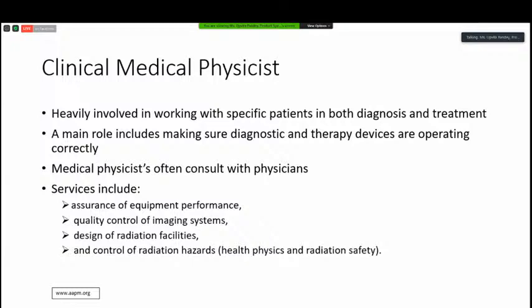A day-to-day job of a clinical medical physicist includes performing quality assurance on treatment machines, checking calibration, checking spatial accuracy of treatment delivery, and checking the quality of treatment plans developed by radiation therapists. They also manage commissioning of new treatment technologies, quality control of imaging systems, designing new radiation facilities, and controlling radiation hazards. These are a few day-to-day roles of a clinical medical physicist.